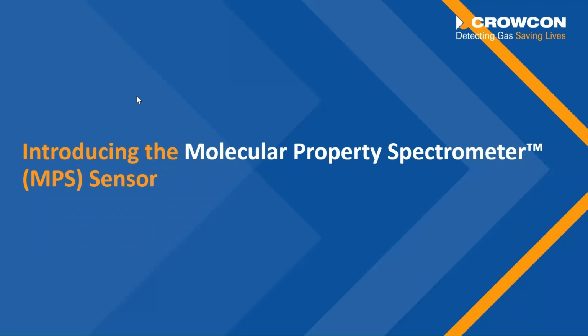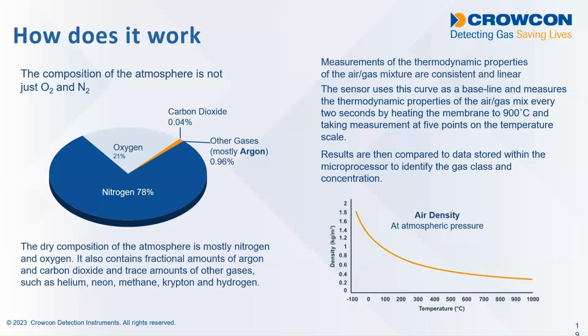So I've outlined the two traditional sensing technologies for flammable gases that have been relied upon for decades. So there's still the two main sensing technologies. However, there is a new sensor that's become available called the MPS sensor, the molecular property spectrometer, which is a real game changer in our industry and is absolutely ideal and has come just at the right time to solve the problem of detecting hydrogen in a dependable way. So the MPS sensor works on the principle that the normal composition of air is fairly defined and stable.